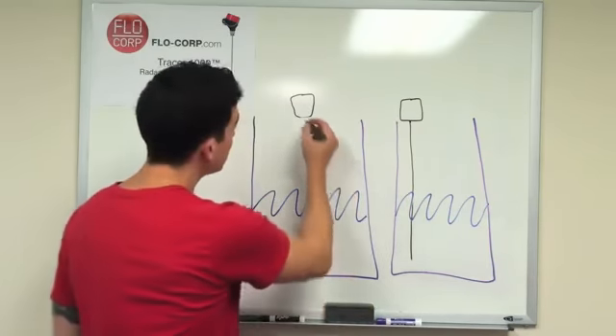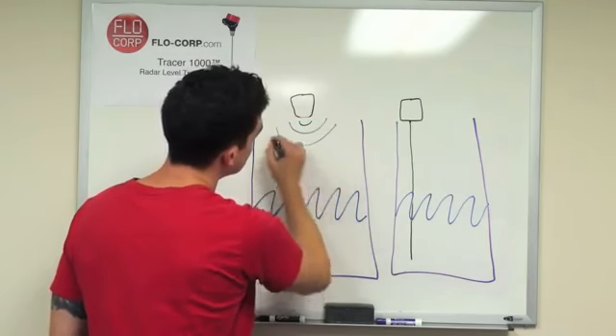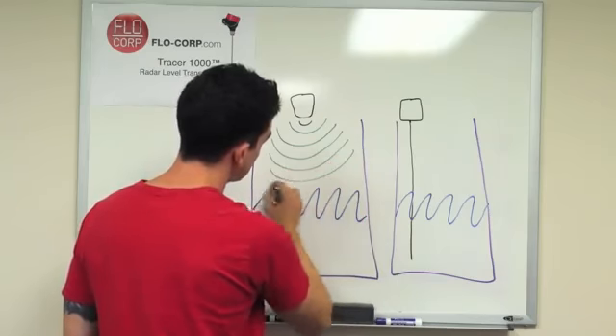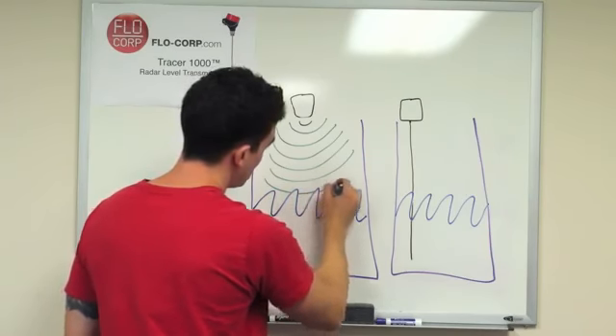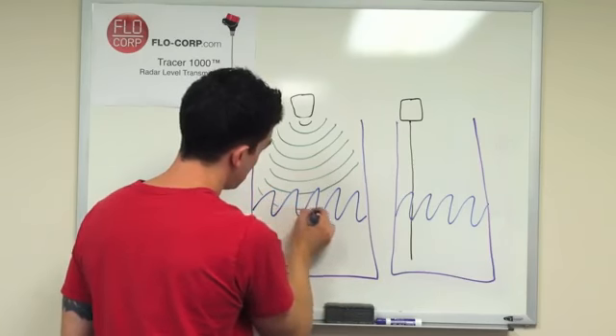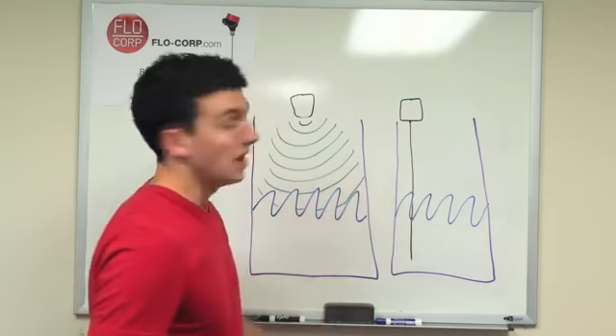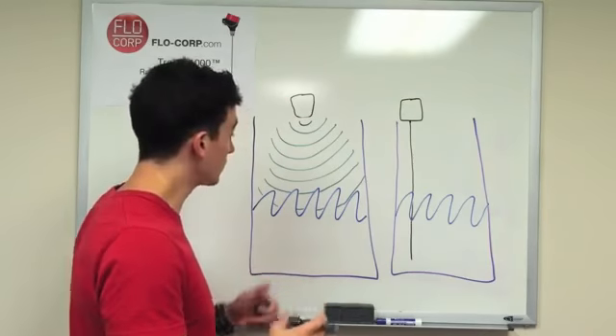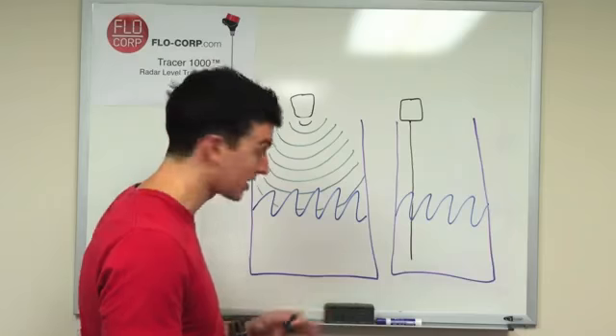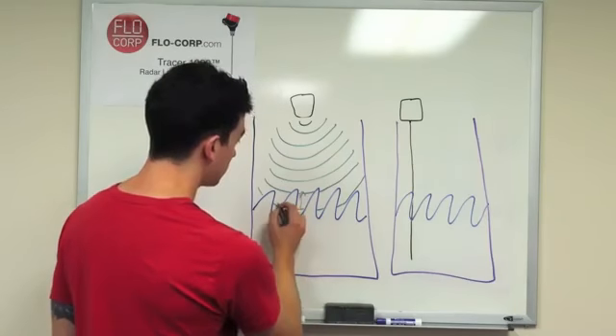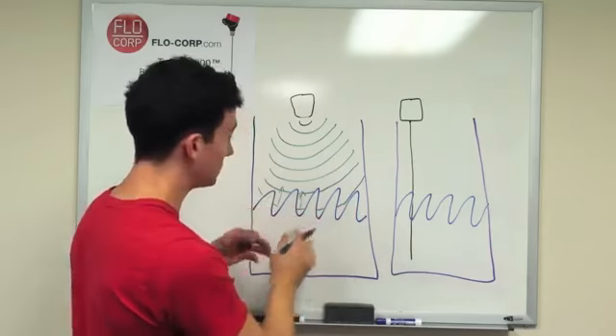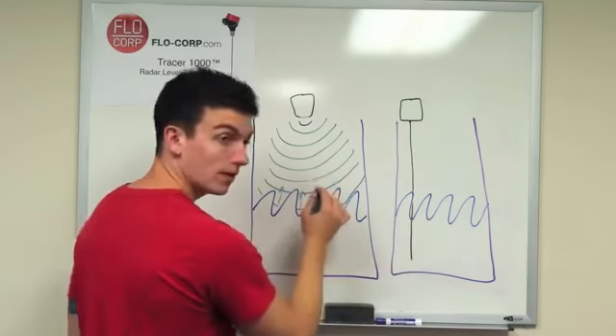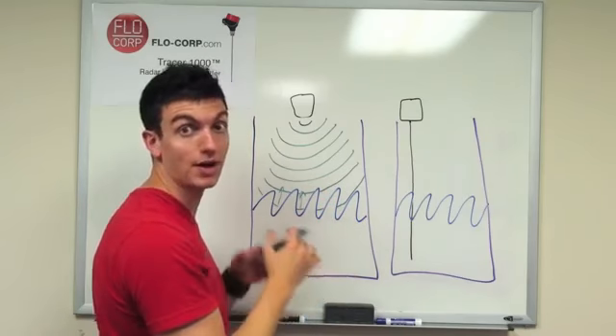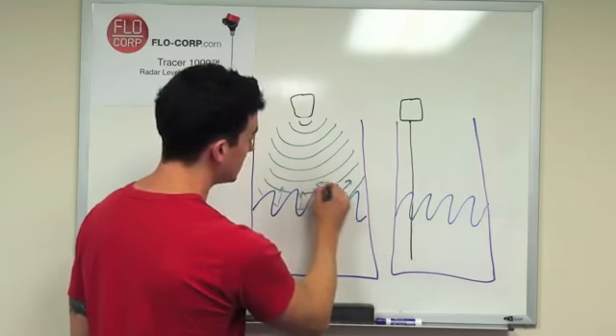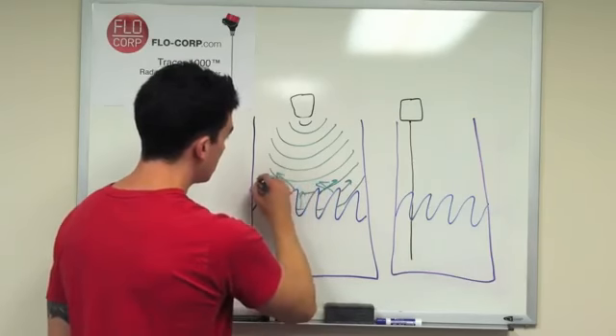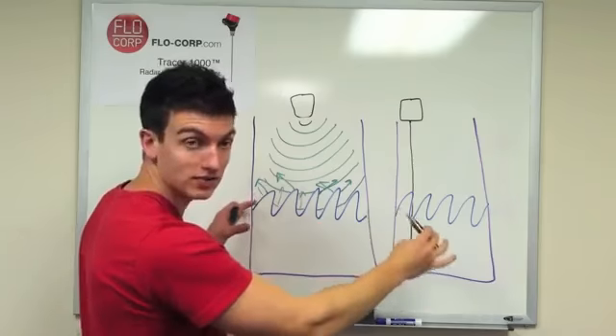So essentially the signal will come down. And it will strike the surface of the liquid we're measuring, and then we're going to get some interesting echoes here. We're going to get some that come straight back up just based on how the turbulence is happening. But what becomes problematic in this situation is we're going to get some other echoes. We're going to get some coming off this direction and this direction. And essentially it's going to bounce off the sides of the tank.